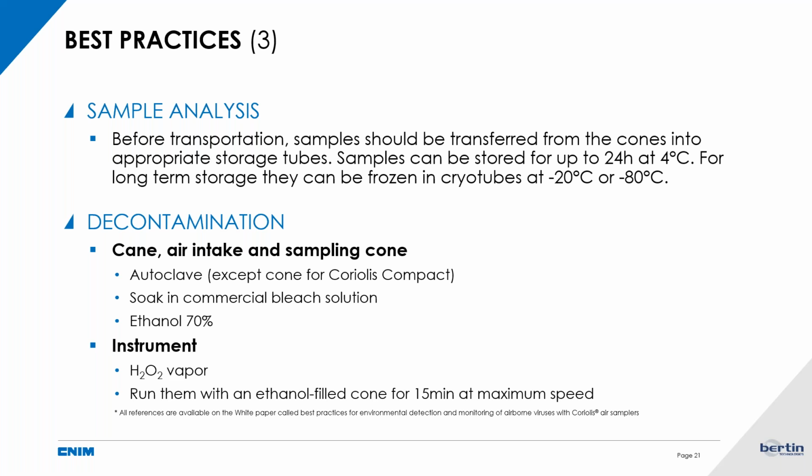And also for the inside of the instrument, if you don't have a device that generates H2O2 vapor, you can put ethanol 70% in the cone, turn on the device and make one or two runs of 10 minutes until the ethanol has evaporated. In this way, it will mainly deal with SARS-CoV-2, but I want to say that this kind of method won't be enough to kill, for example, spores.